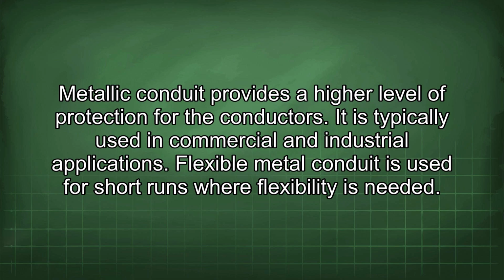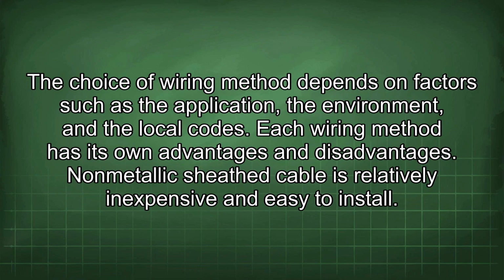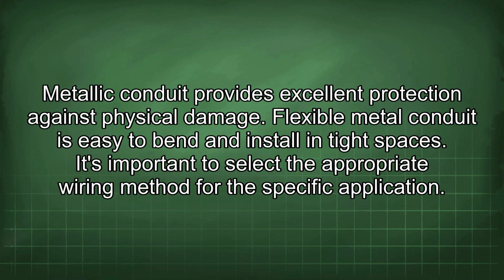Metallic conduit provides a higher level of protection for the conductors. It is typically used in commercial and industrial applications. Flexible metal conduit is used for short runs where flexibility is needed. The choice of wiring method depends on factors such as the application, the environment, and the local codes. Each wiring method has its own advantages and disadvantages. Non-metallic sheath cable is relatively inexpensive and easy to install. Metallic conduit provides excellent protection against physical damage. Flexible metal conduit is easy to bend and install in tight spaces. It's important to select the appropriate wiring method for the specific application.